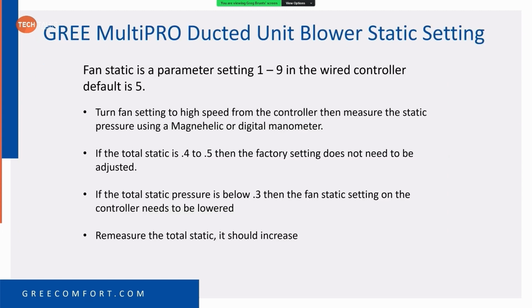Another thing about ducted units. Whether it's an air handler or a ducted unit, airflow is a big deal, because now we're adding ductwork into it. All of the controllers come pre-wired and preset in the parameters at a default of 5, and you can set the static curve between 1 and 9. To adjust for static pressure on the controller, turn the fan on high speed, let the fan run, and measure your total static pressure drop across the air handler.